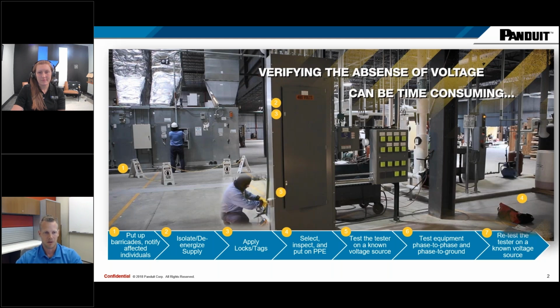And then getting into the bread and butter of the inspecting and then checking your meter, going in and checking your panel, both phase to phase and phase to ground. So 6 measurements, 7 with that neutral ground if it's a service entrance, as Caitlyn pointed out, and then going back to that same convenience outlet and confirming that your meter is working on both sides of the measurements, right? That live, the bookended live, I'll say, is important to get both sides. It's not just a live dead test, it's a live dead live test.